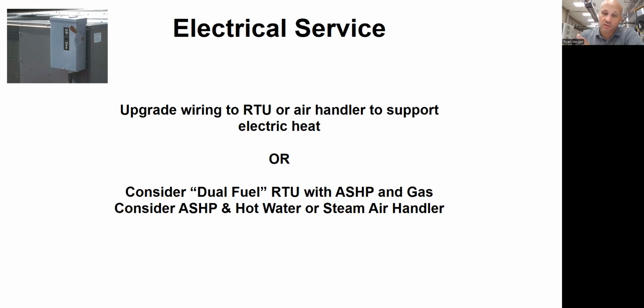On a split system, I have the indoor component that already has either a gas-fired heat exchanger in it, a duct furnace basically, or it has a hot water coil that's connected to a gas-fired boiler, right? So in those cases, I would leave the air handler alone. I would leave the boiler plant alone. I would just swap the outdoor unit to a heat pump version of that, and I would not change anything else. I shouldn't say that. I have to change the thermostat wiring. I need more wires. But I wouldn't have to change the high voltage wiring because I'm not adding electric resistance heat to the indoor unit. I'd just run my fan like normal off of that.